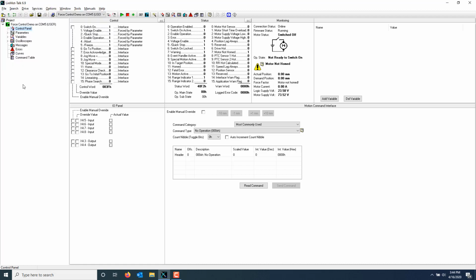Additional hardware is also required. A load cell is used to measure the force, and a signal conditioner should be used to ensure that there is no noise. The drive is capable of accepting inputs between 0 and 10 volts on its single-ended analog input and negative 10 and 10 volts on its differential analog input. Make sure that the load cell outputs a clean signal, is well matched to the load that will be measured, and is capable of measuring dynamic forces.